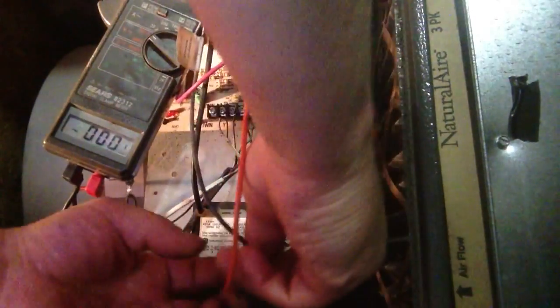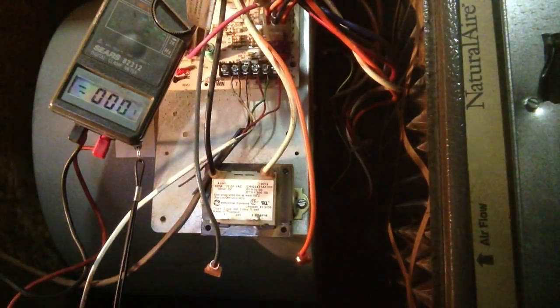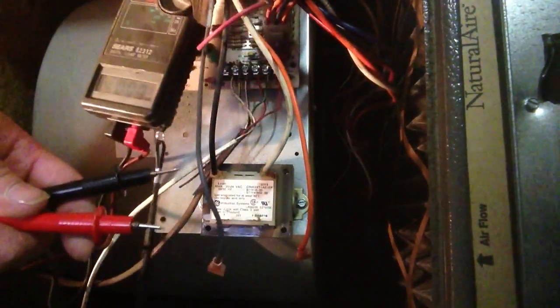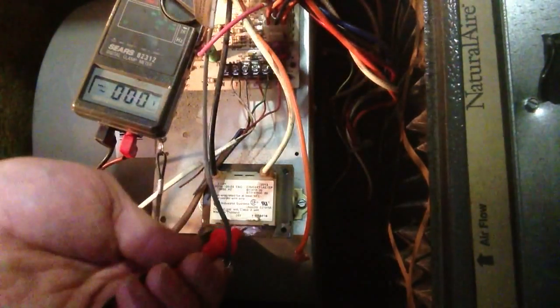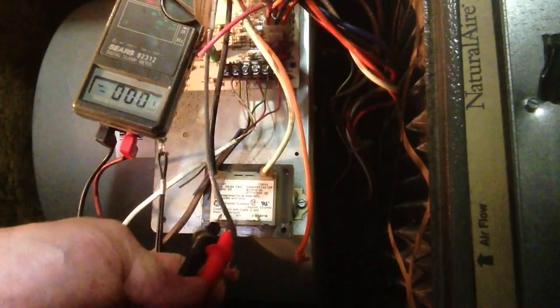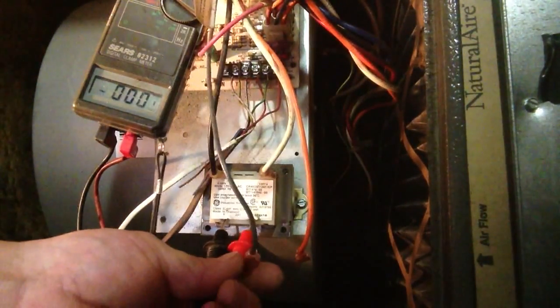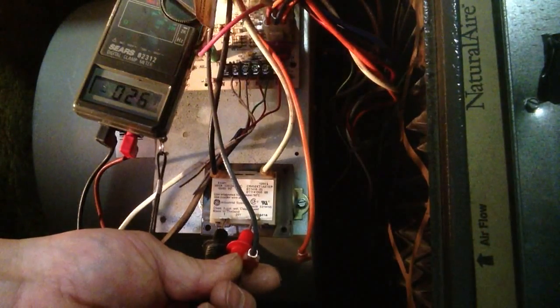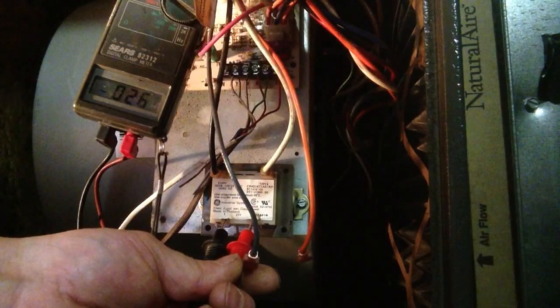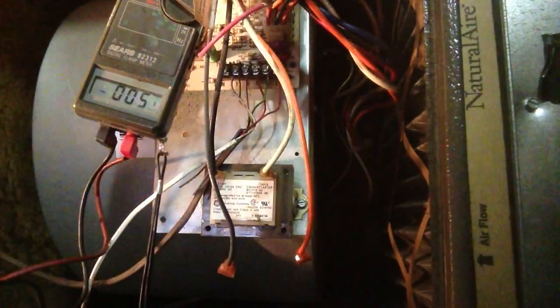But we're going to go ahead and make sure we have our voltage. We're going to take the two wires off the bottom of the transformer. We're going to put our leads on there. I'm using a nav probe, but you can use a multimeter. And we'll give that a quick test. And it says we have 26 volts. So our transformer is working.